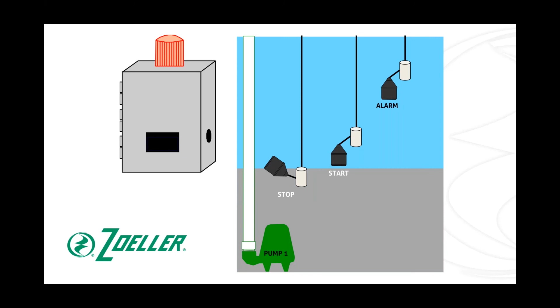So let's run through this again. Water begins to rise in the pit. The stop float is activated. Nothing happens. The start float is again activated. The pump begins to pump water once again. But this time, let's say the flow of water that was coming into this pit was so great that the pump couldn't keep up with that flow.